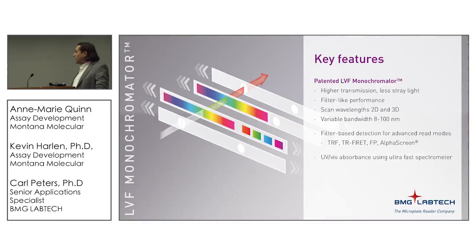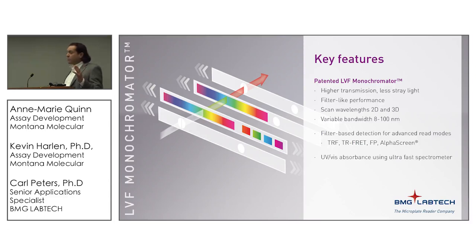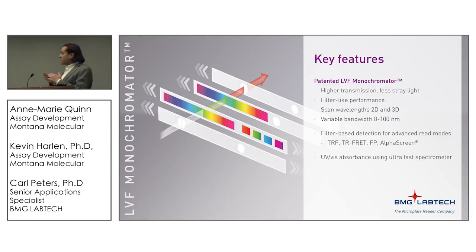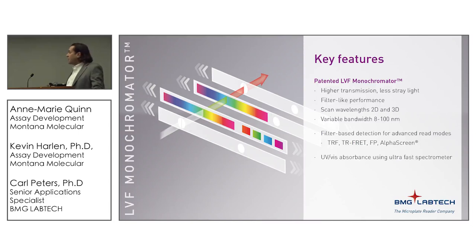The key feature of the ClarioStar was the patented linear variable filter monochromator — literally glass slides that let you select the rising and falling edge of the wavelengths passing through. It has very good light transmission, providing filter-like performance while retaining the selectability to do the two different wavelengths for red and green proteins. For development purposes, you can do excitation-emission scans to focus in on appropriate wavelengths. It can also be used filter-based for highest sensitivity, especially in cell-based assays.